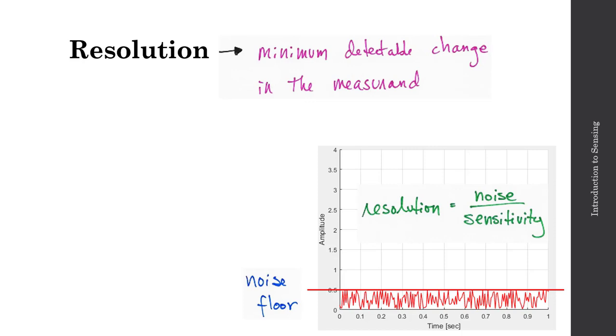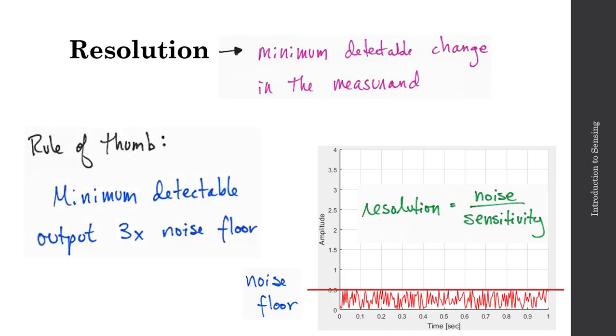And so we can define resolution as the ratio of this noise divided by the sensitivity. And what we see here is that noise is in output units, and sensitivity is the ratio of that output over input. So those output units cancel, and the resolution will be in units of the input. A good rule of thumb to use in terms of the resolution of a sensor is that the minimum detectable output is typically about three times the noise floor.